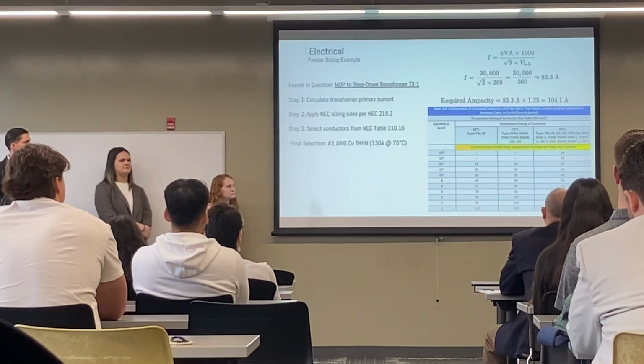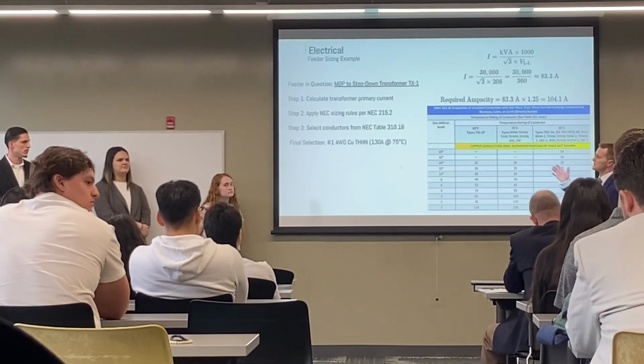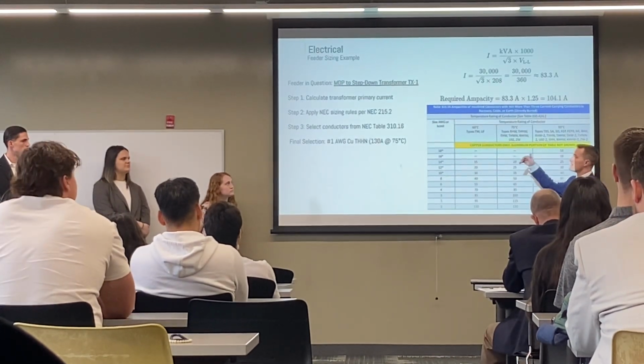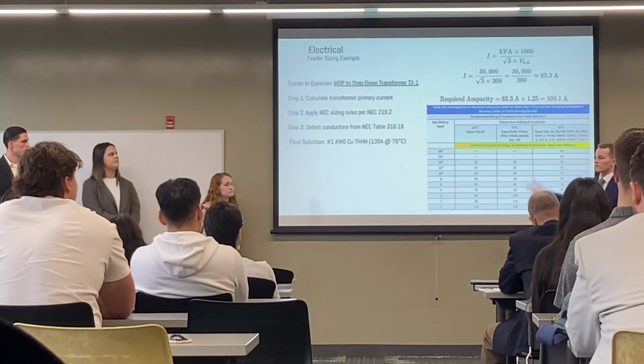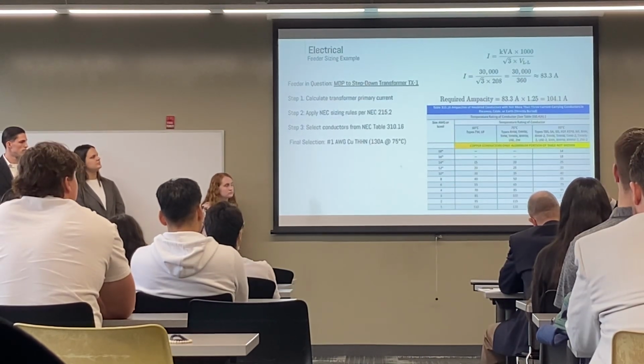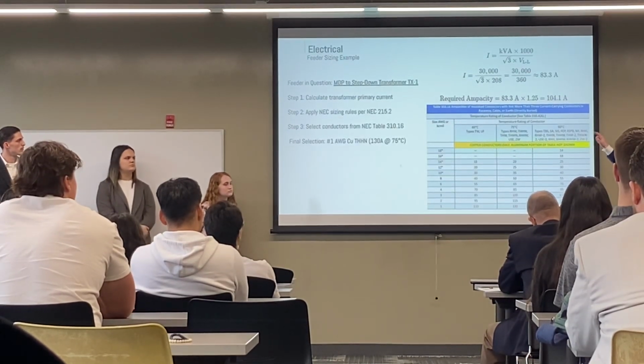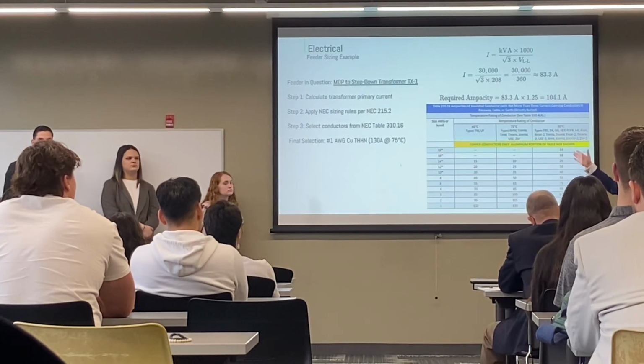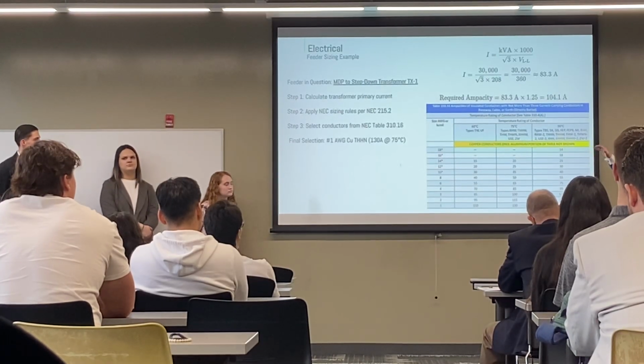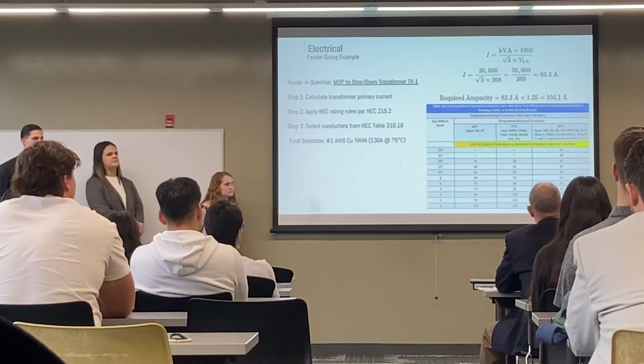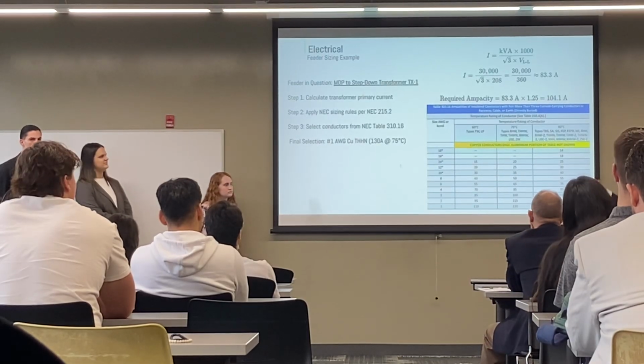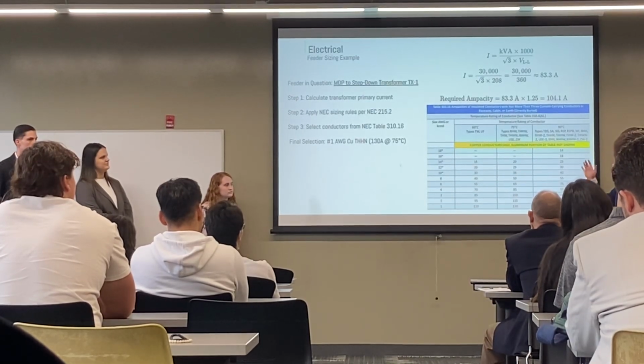Now here is a feeder sizing example. The one we're going to go through is the main distribution panel to the step-down transformer TX1. The first thing you do is calculate the transformer primary current. That's the top equation: the current equals the kVA times 1,000, to get it to VA, and you divide that by the square root of 3 times the line-to-line voltage, which in this case is 208. You do that and you get 83.3 amps.